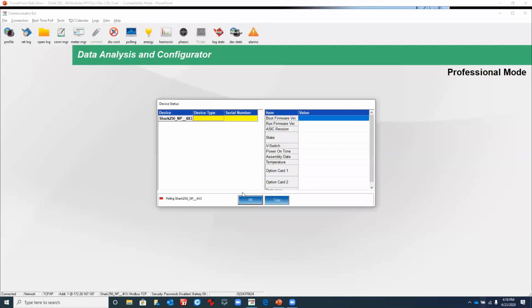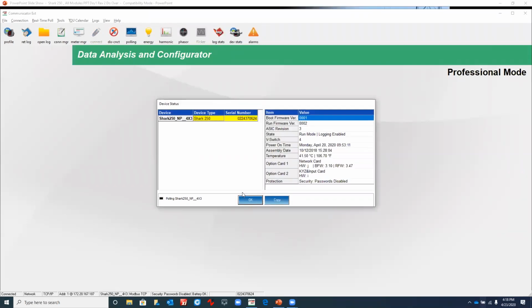There we go. When you first connect to the meter, you see the Device Status box. In that window, you will be able to see the device name, the meter name, the device type, which is a Shark 250, and the serial number. In the other half of the screen, you'll see the firmware version: the boot, firmware version 1 in this case, run version 2, ASIC version 3, and state. V-Switches are very important, and we'll touch on that briefly as we go further in. There's also the assembly date, date of manufacture, temperature, and what other option boards are installed. So we know the network card was one of the option boards we talked about, and there's also in this meter a KYZ board, which is option 2. We'll talk about those as we go further along.